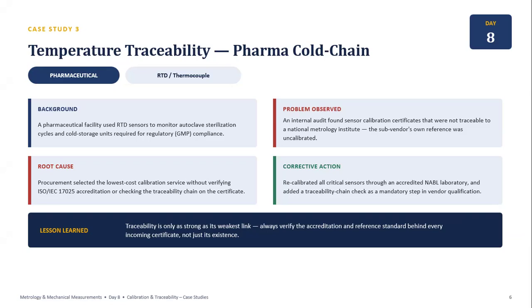The corrective action was to recalibrate critical sensors through an accredited NABL laboratory and introduce traceability verification as a mandatory part of vendor qualification. The key message is that traceability is only as strong as its weakest link. Never evaluate a calibration certificate merely by its appearance or existence. Verify the accreditation and the reference standards supporting it.